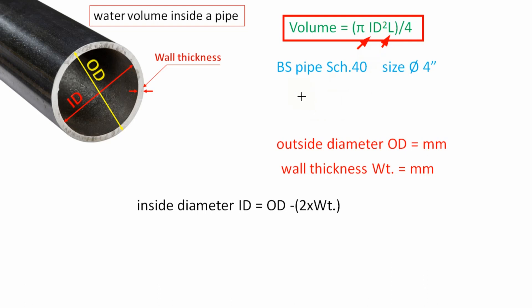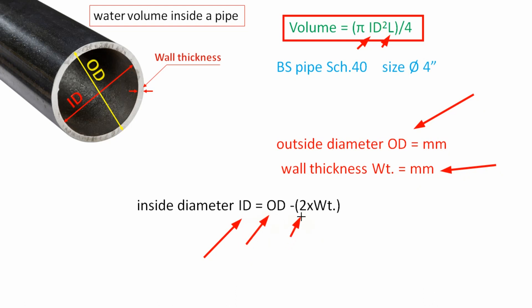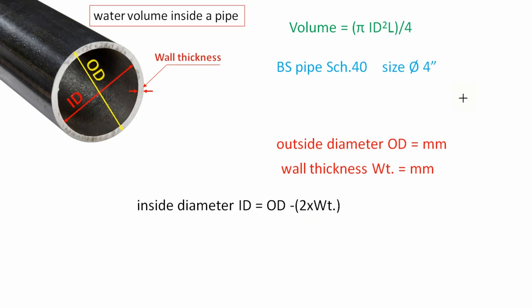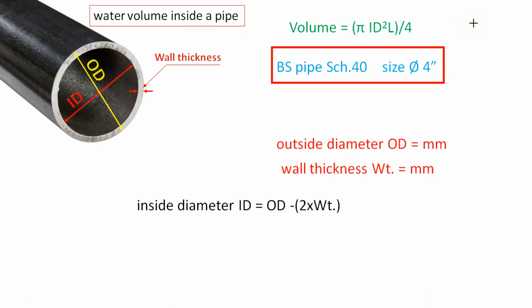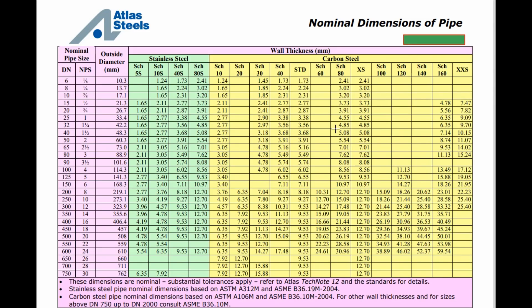From the pipe properties table, we can select the pipe outside diameter and pipe wall thickness. To calculate the inside diameter, we use this formula: pipe inside diameter equal to pipe outside diameter minus 2 times pipe wall thickness. For our sample calculation, let us assume we have a black steel pipe, schedule 40, diameter 4 inch.